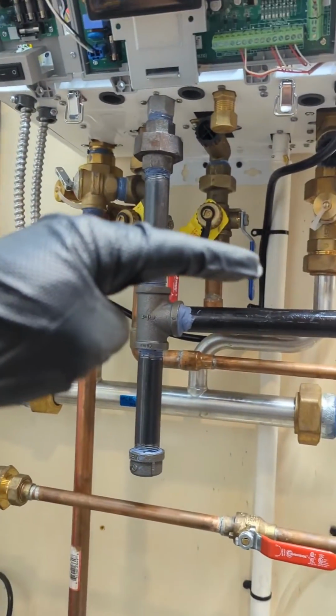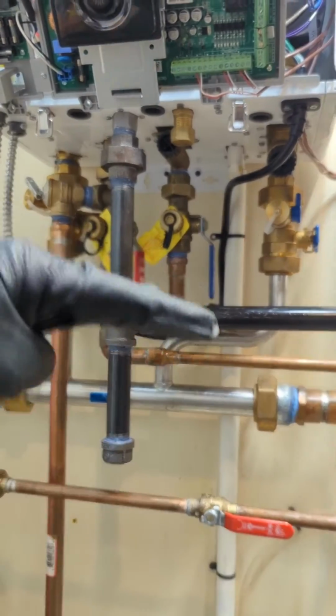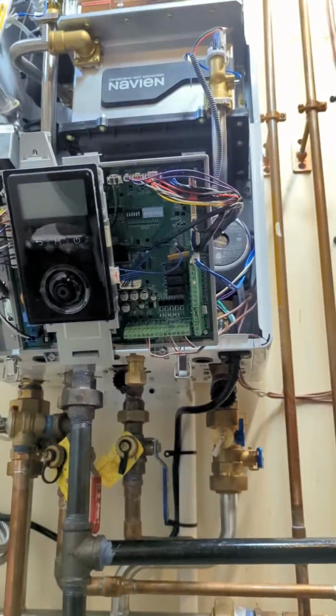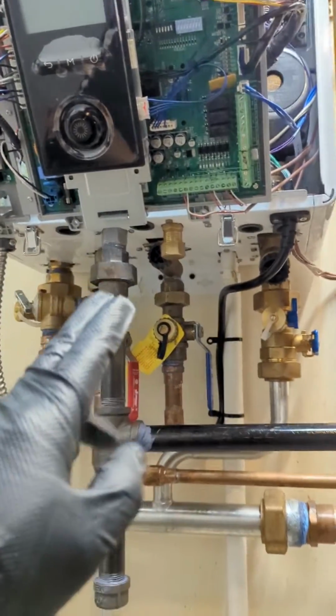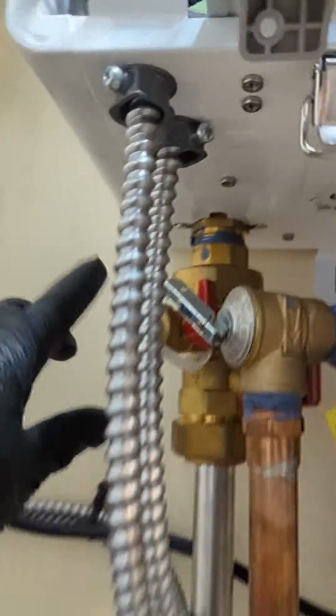So you've isolated the distribution baseboard side from the boiler side. Now you still have pressure inside, so you have to drain the water out using this boiler drain here.